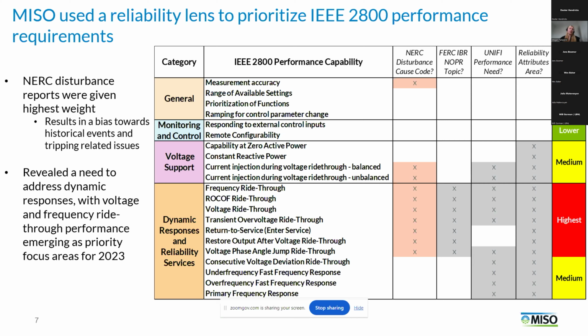And to do that, we mapped the inverter loss of generation cause codes for each event to the 2800 requirement that could have prevented or maybe addressed that issue. We also considered potential future grid needs through 3 other prioritization sources, including the FERC IBR NOPR, which led to Order 901. And on the far right-hand side of the table here, you can see the resulting priority of each capability based on all 4 of our prioritization sources and dynamic responses. Specifically, most of the ride-through capabilities bubbled up to the highest priority, as shown in red there.